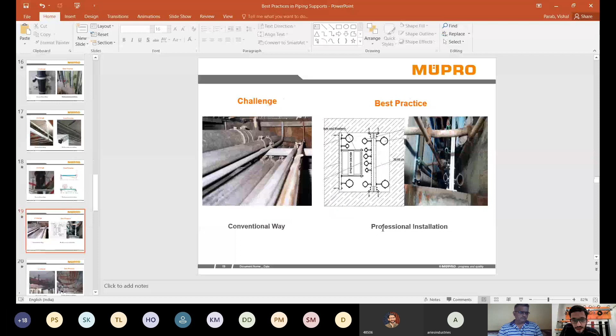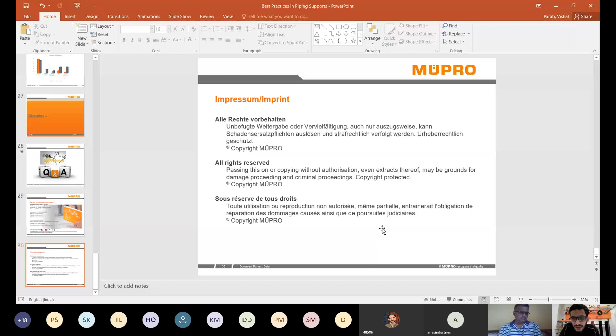Fine. And one more question is, what is the galvanizing in terms of microns? How much galvanizing do you have for your supports? Sir, it is 275 GSM, around 20 microns for galvanization. And for hot dip galvanization, it is more than 40 microns. I think for Mumbai climate, 40 micron would be less if it is exposed. So a minimum of 40 microns, it can be achieved more than 40 micron as per the requirement. If you want 60 micron, we can give you 60 micron.